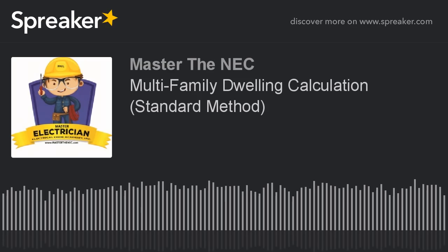But now we have to find out what demand factor we can apply for the 18 dryers. Now, how do you do that? Well, you notice that it says in 220.54 that the demand factors in table 220.54 shall be permitted. Obviously we want to use them because the demand factor is going to result in a smaller service value. So it says we're permitted to do it, so we're going to do it. If you go look at table 220.54, you'll notice that it has a number of dryers.